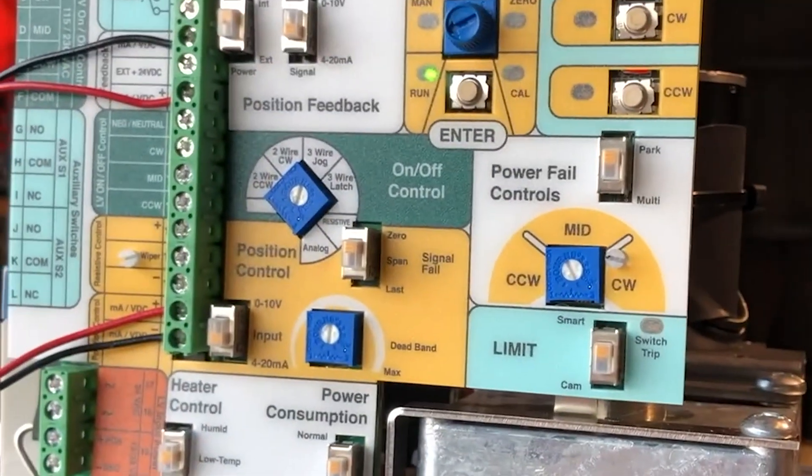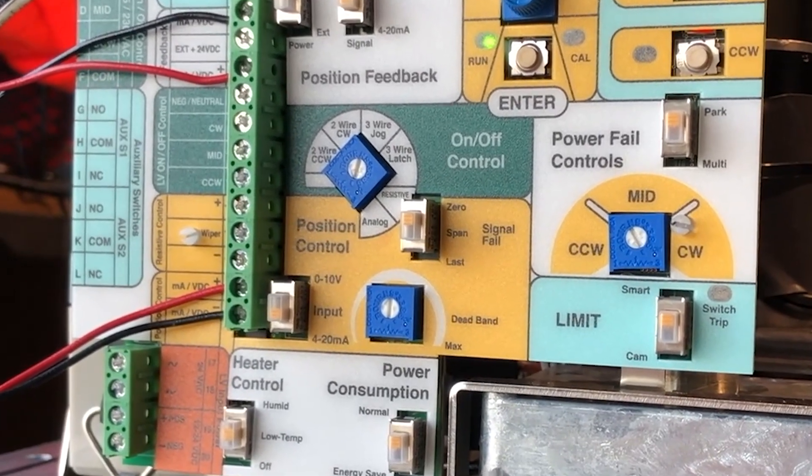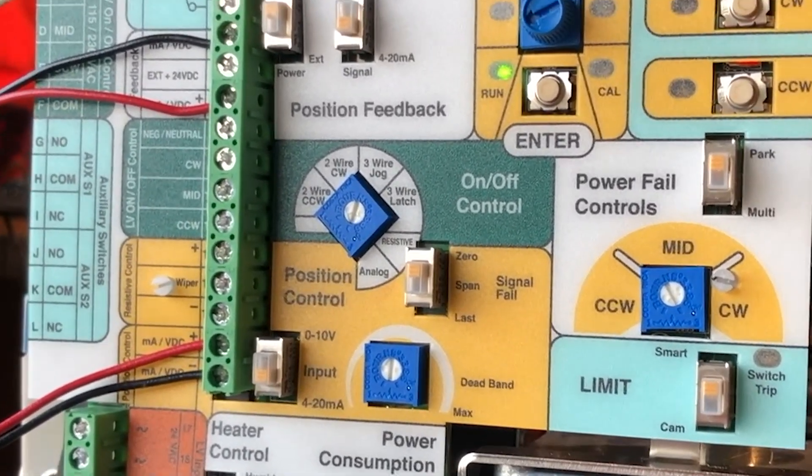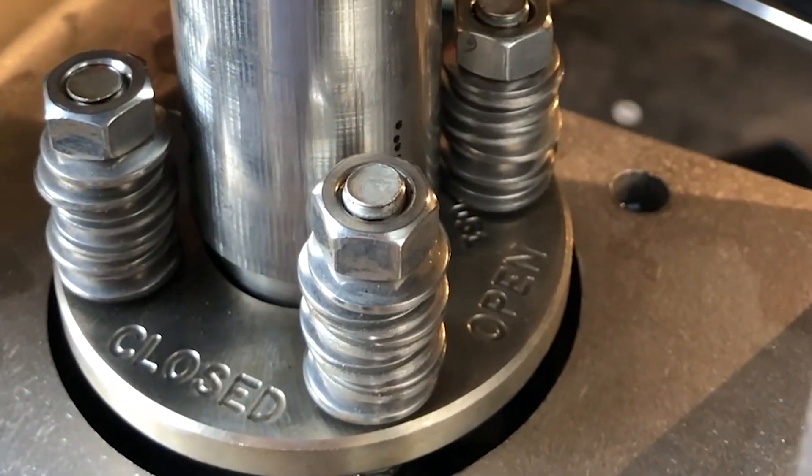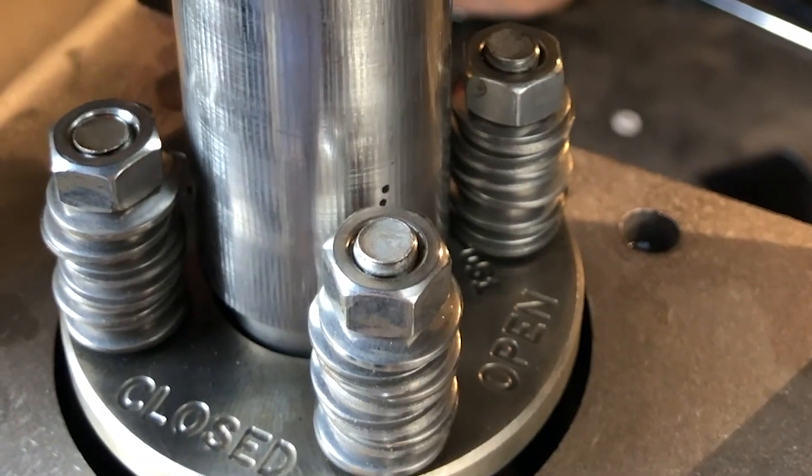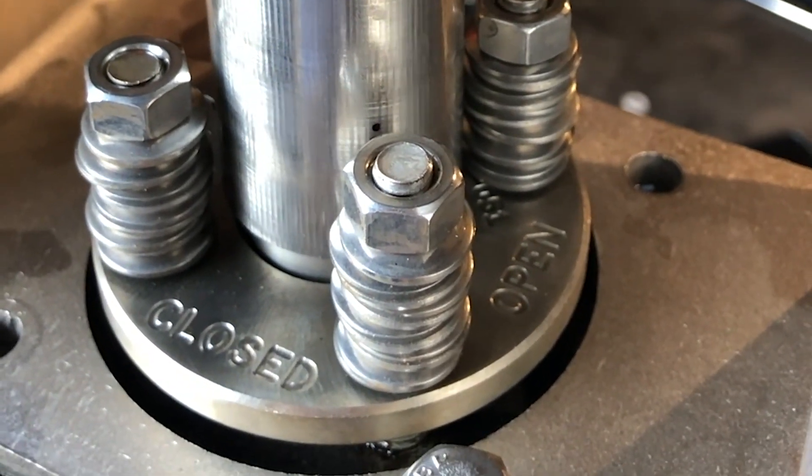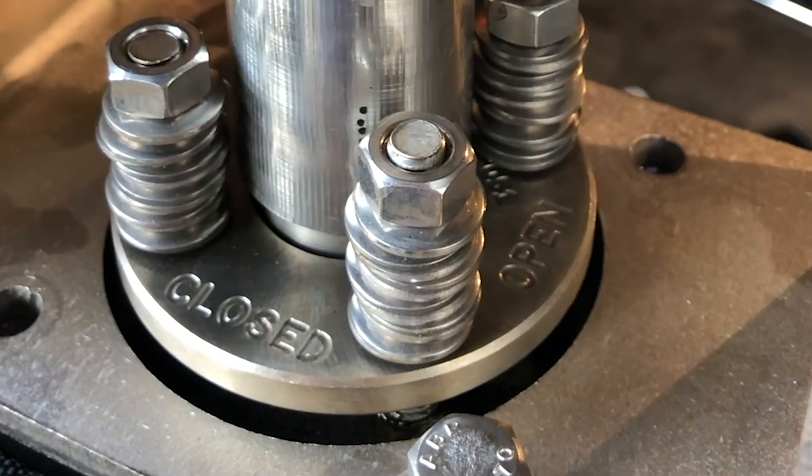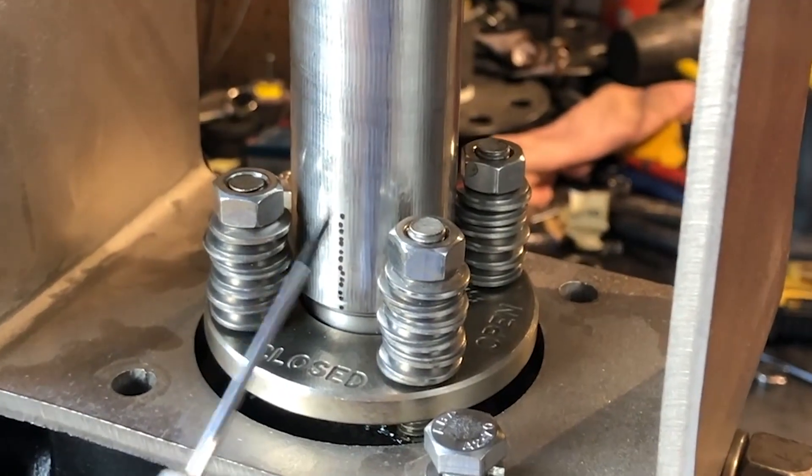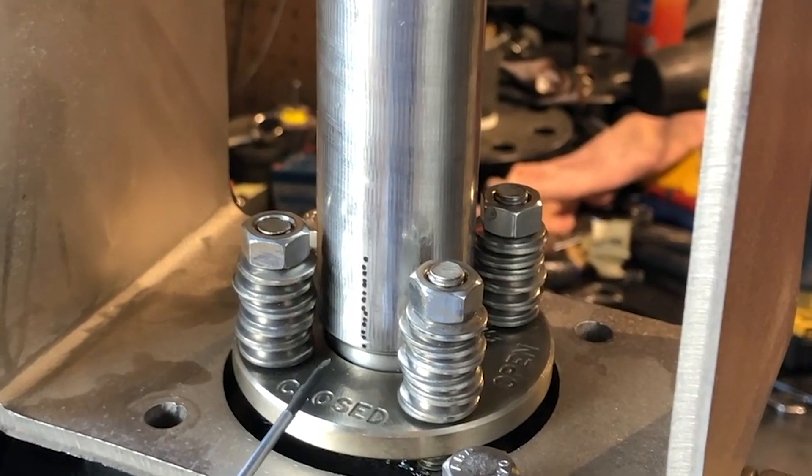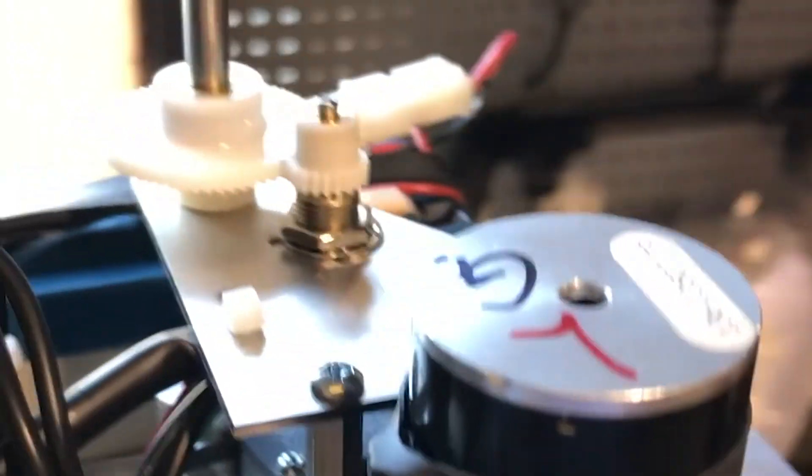The last thing to check is your fail closed position with the loss of power so I'm going to kill my source voltage and the valve should come back to the complete closed position. You can verify that with your indicator on your shaft of your valve. And also by the notch on the main shaft of the actuator.